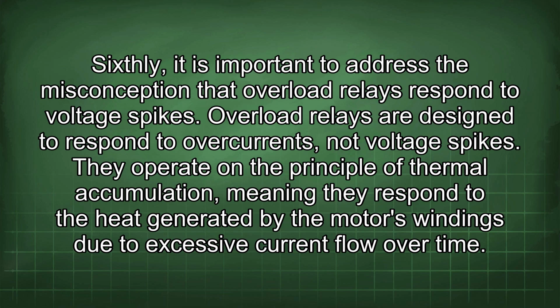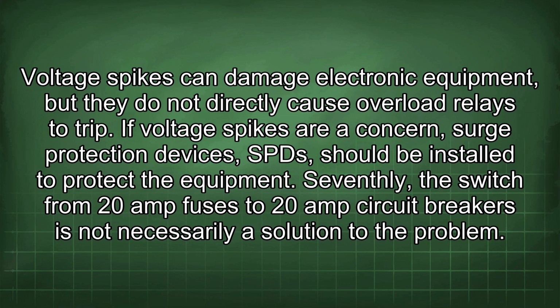Overload relays are designed to respond to overcurrents, not voltage spikes. They operate on the principle of thermal accumulation, meaning they respond to the heat generated by the motor's windings due to excessive current flow over time. Voltage spikes can damage electronic equipment, but they do not directly cause overload relays to trip. If voltage spikes are a concern, surge protection devices, SPDs, should be installed to protect the equipment.